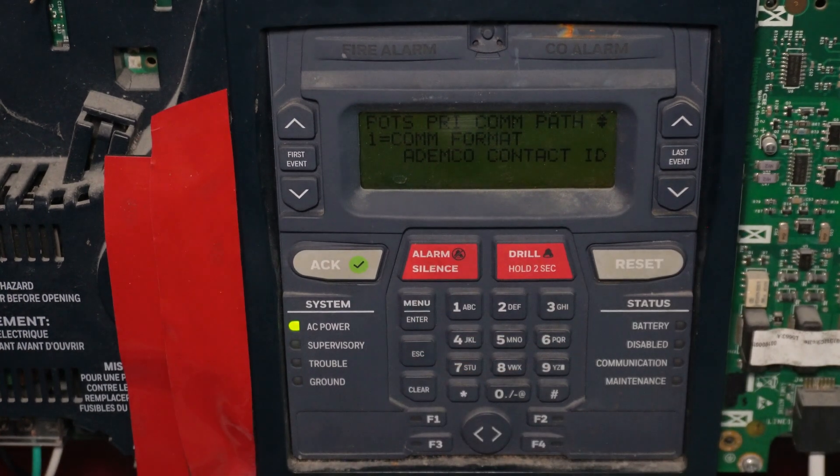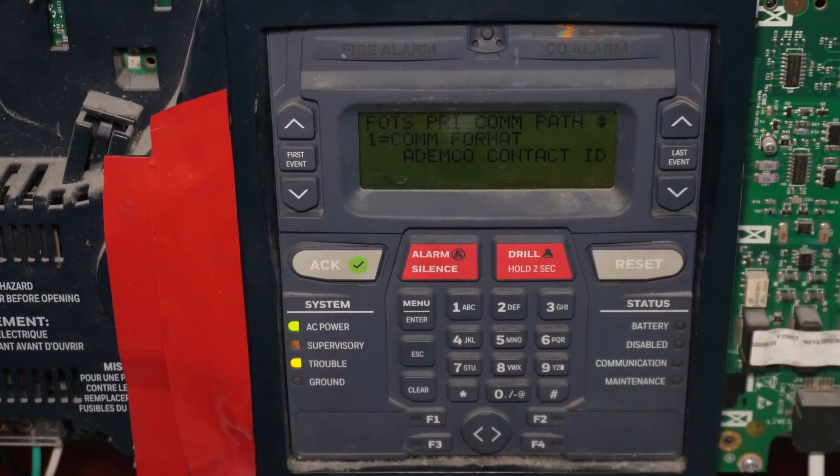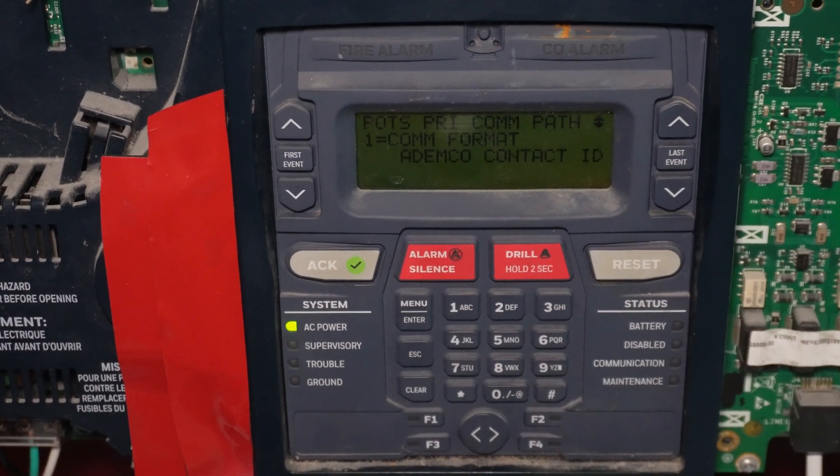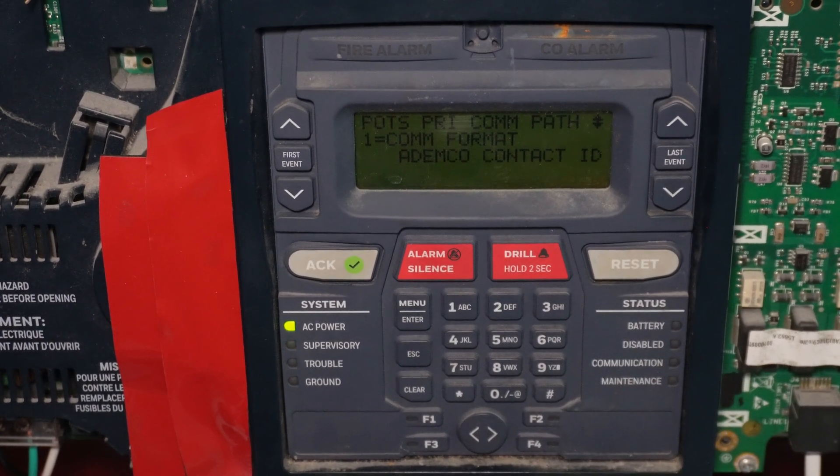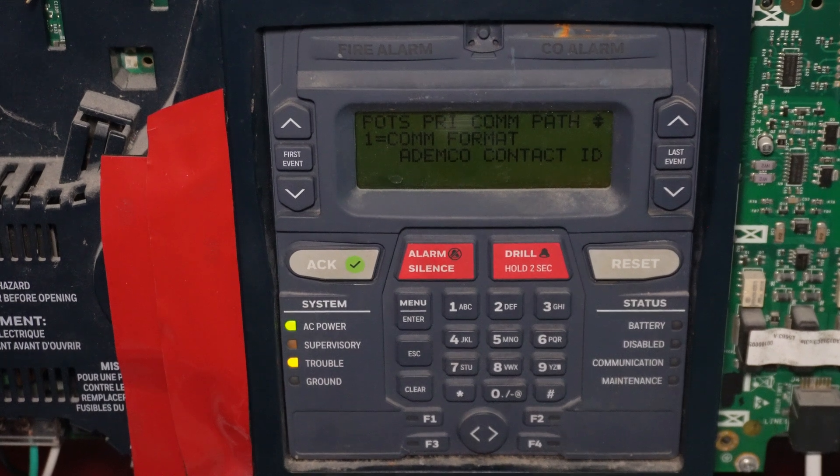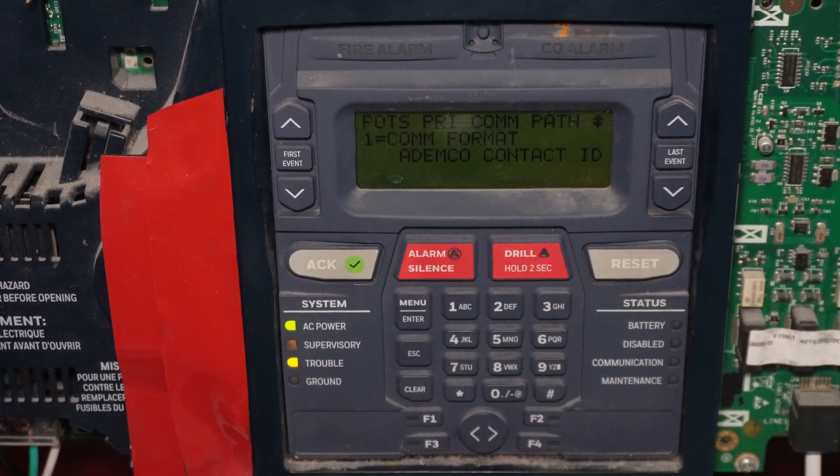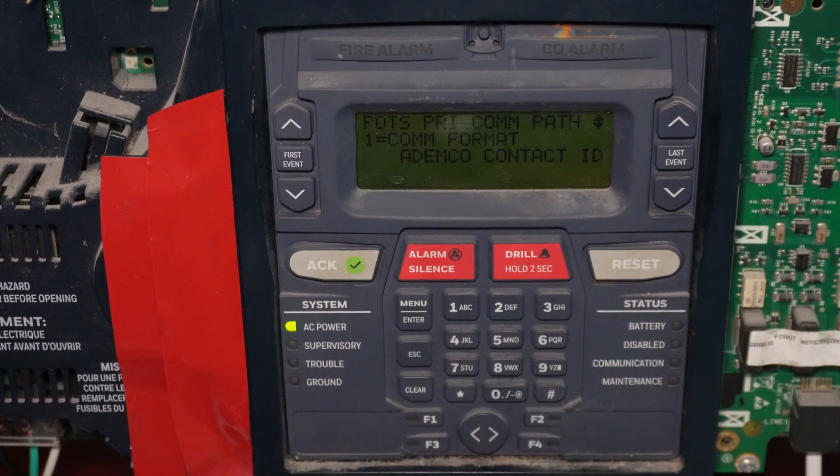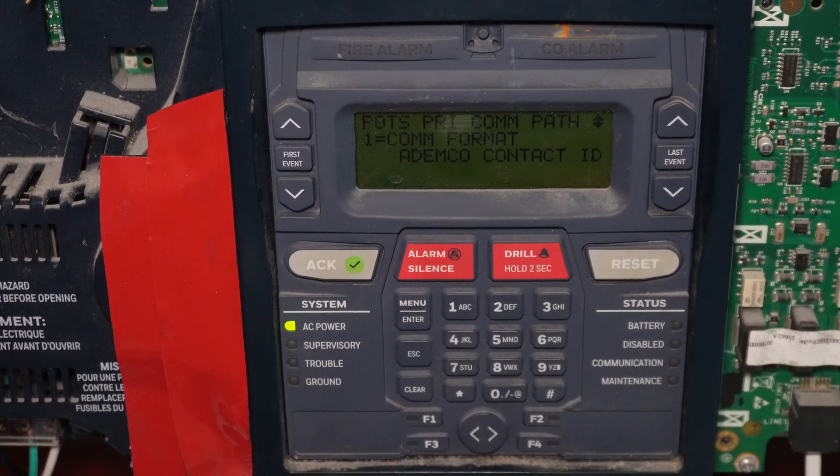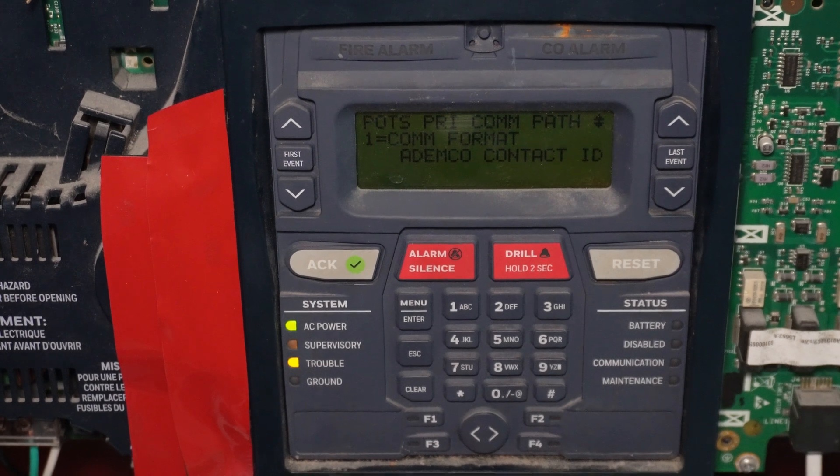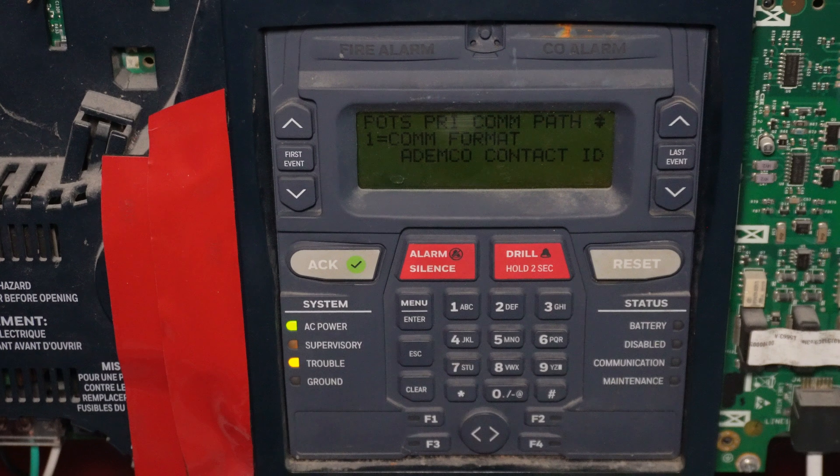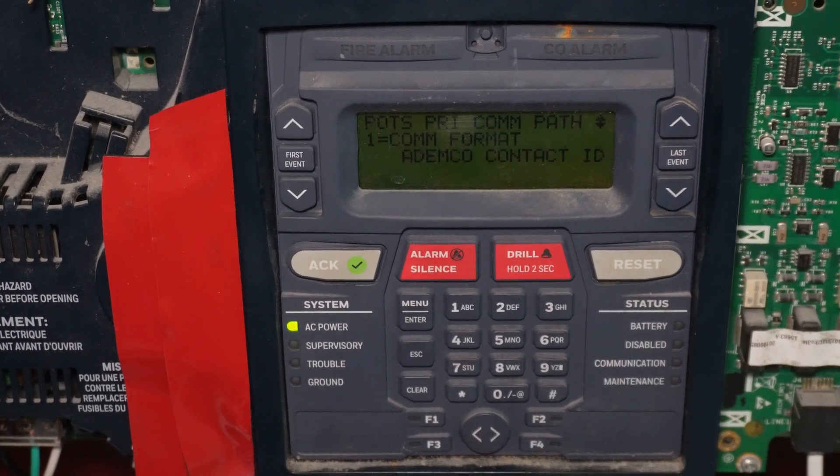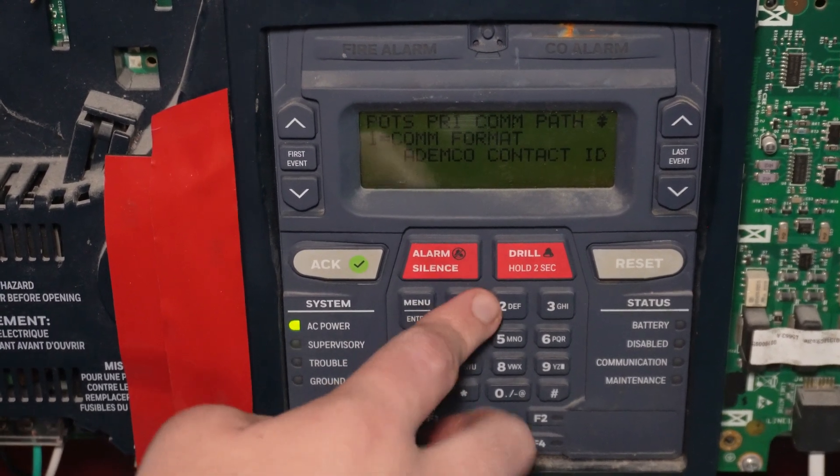And then the communication format. Right now it's set to contact ID, which there's nothing wrong with that. Except the fact that probably on most modern phone lines that's not going to work so well due to digitation. And the fact that the contact ID digits are just going to keep getting garbled up when it's trying to transmit. And the central station receiver is not going to understand the signals it's trying to relay. So I'm actually going to change that.